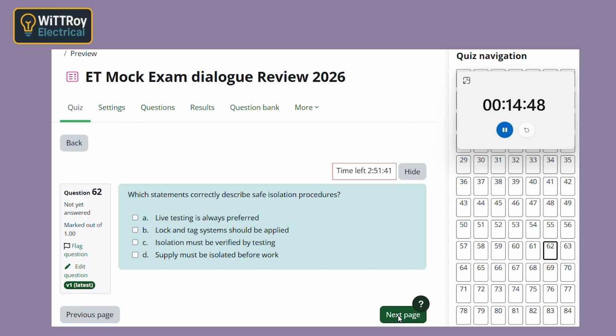Question 62. Safe isolation procedures. Supply must be isolated, tested, and locked and tagged. Yes, let's go through why each one matters. First, isolate the supply. That removes the normal source of danger. Then verify isolation by testing. That is critical because you must not assume isolation is effective just because a switch was operated. So testing confirms it is actually dead.